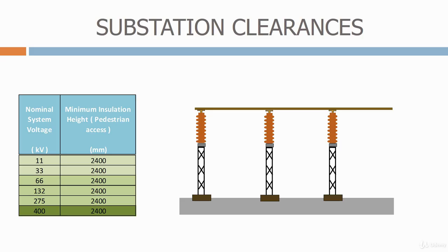To do this, we make sure that all insulators are raised a certain distance from ground level. As this is a safety clearance, the minimum distance of 2.4 meters applies across the full voltage range. The clearance distance is taken from the ground, or anything that personnel can stand on, to the bottom of the insulator. This includes the insulator foundation. But you will find that for the higher voltage levels, the sectional clearance takes precedence, and the bus bars are raised even farther off the ground.